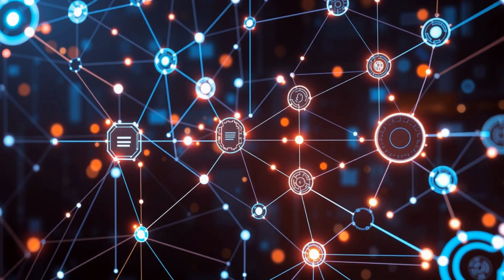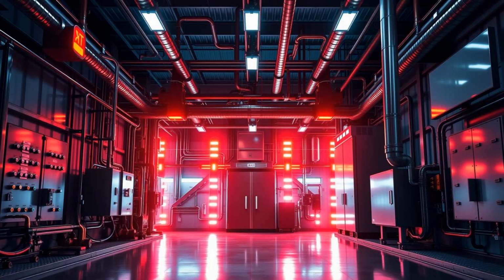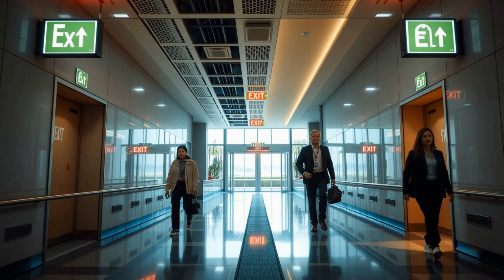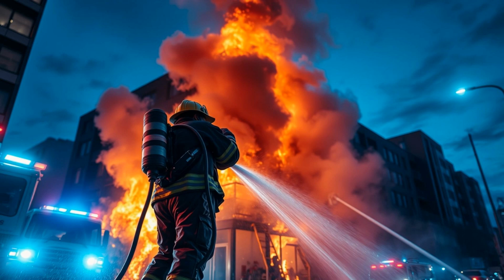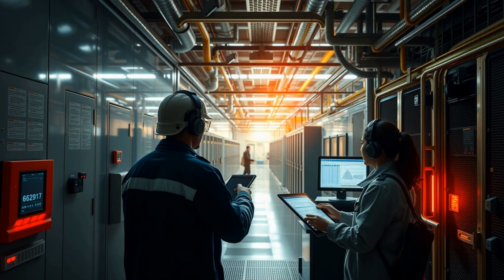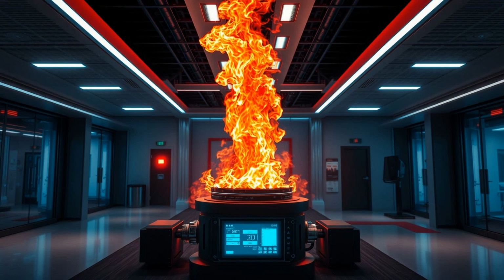It is not a singular device or tool, but a comprehensive network of components that work together to minimize risk and maximize safety. At its core, a fire protection system serves three primary objectives: life safety, property protection, and operational continuity. Life safety focuses on ensuring that building occupants have early warning and safe routes for evacuation. Property protection involves controlling or extinguishing the fire before it causes significant structural damage. Business or operational continuity is often overlooked but critical. In high-value facilities such as hospitals, airports, data centers, and manufacturing plants, even a few minutes of fire-induced downtime can lead to enormous losses. Thus, the modern fire protection strategy doesn't just fight fire, it fights its consequences.